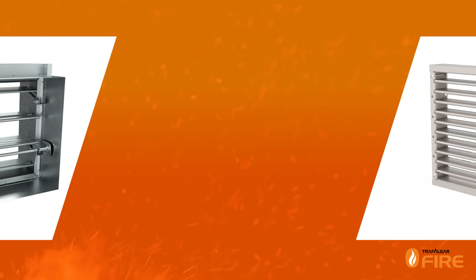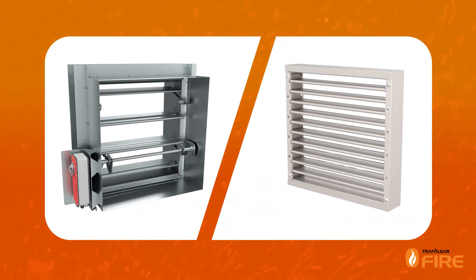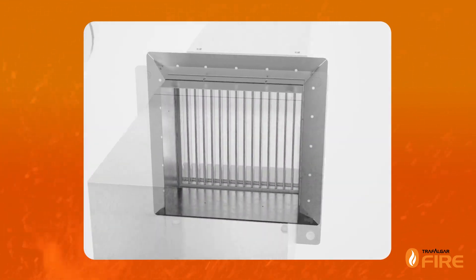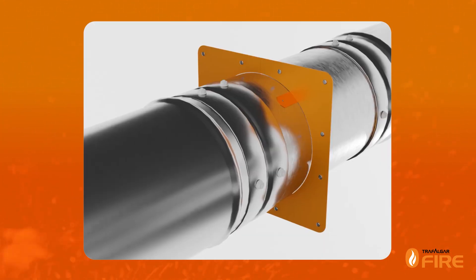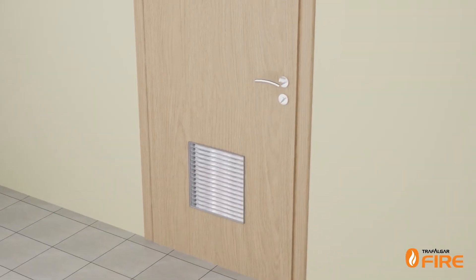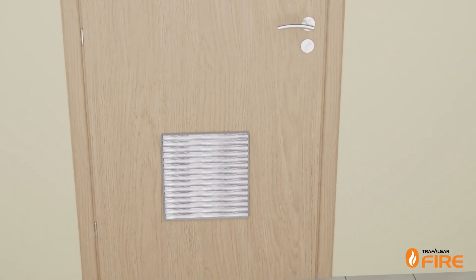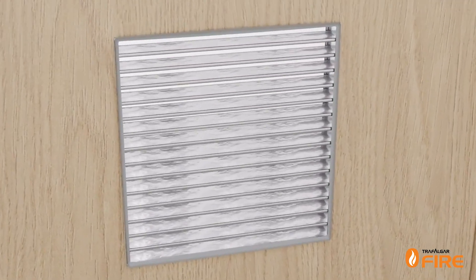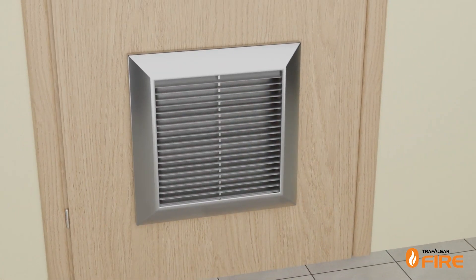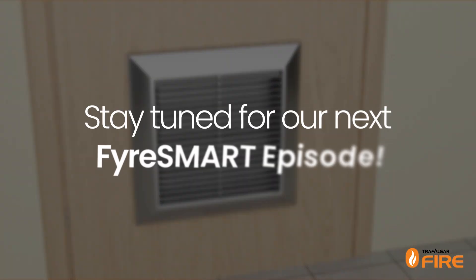Over the last 30 years, intumescent fire dampers in Australia have become a respected alternative to conventional mechanical curtain or blade type fire dampers. It is important to note that intumescent fire dampers are ducted, in contrast to fire rated air transfer grills that use similar intumescent technology, which are unducted. Fire rated air transfer grills have very different fire testing requirements and performance criteria, and we will cover these in our next FyreSMART episode.